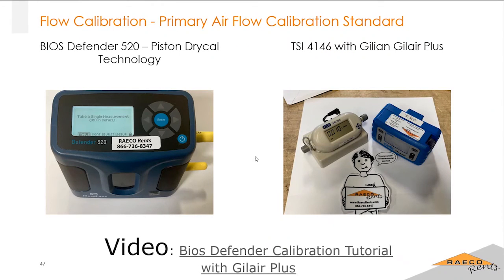And these are the primary flow calibrators. This is a BIOS Defender. You may have heard of these before, like the 510 or the 520. They have different options, like a medium flow, a high flow, a low flow, depending on what you're doing. And then there's a TSI 4146. That one's pretty much good for 0 to 20 liters, so it's pretty versatile. There is one little thing, though, which you can pick up just from looking at this picture.